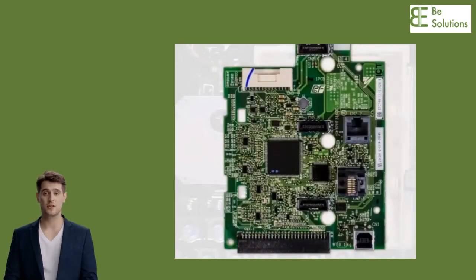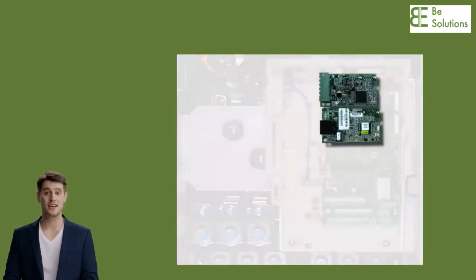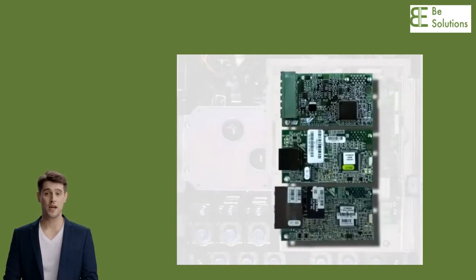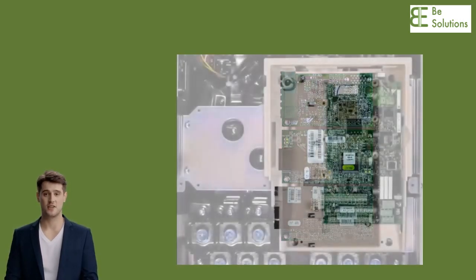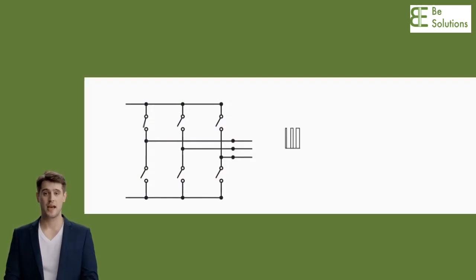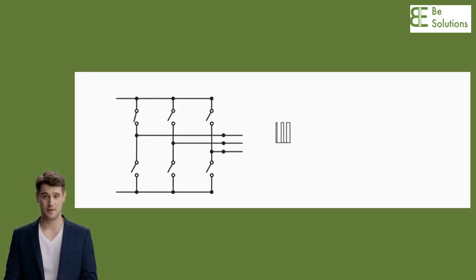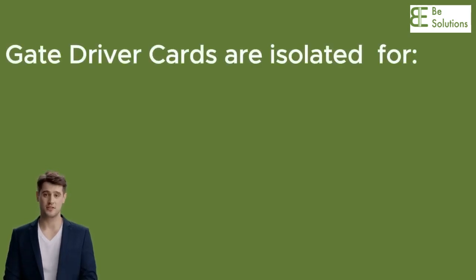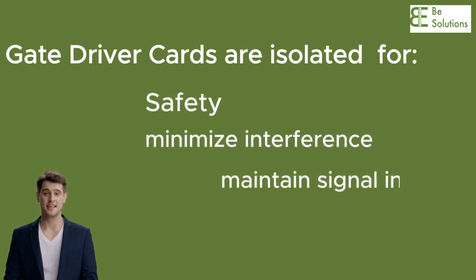The control card houses a microcontroller unit, MCU, which generates the signal to generate PWM, pulse width modulated power flow, in the IGBT. The signal from the MCU card goes to the IGBT trigger card, which drives the IGBT. The IGBT, acting as a switch, can create a pulsating waveform known as a PWM waveform at a rapid pace. The switching rate of IGBTs can be controlled depending upon the desired output. Gate driver cards are isolated in VFDs to ensure safety, minimize interference, and maintain signal integrity.